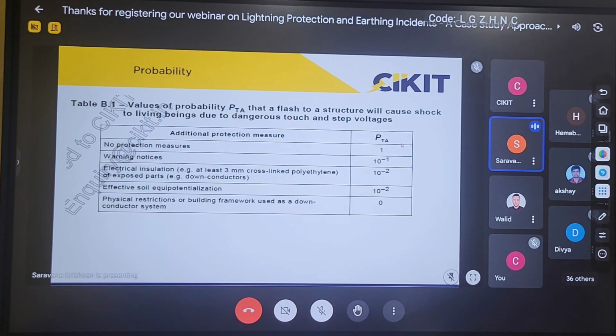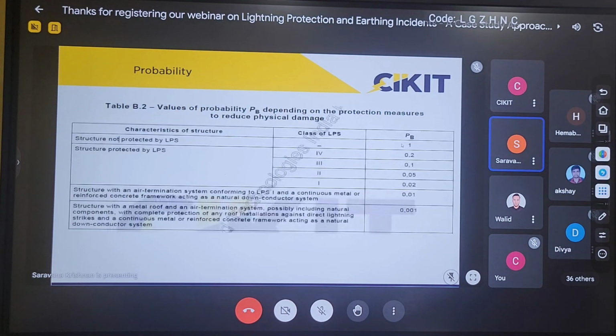So this is the next probability, PB. Here you can observe that if there is no lightning protection system, the value of PB will be considered as 1. If my structure is protected by a lightning protection system, then, depending upon the level of protection, the value of PB will be different. For example, while performing the risk assessment calculation, I will first perform the calculation without a lightning protection system, and then I will substitute the value of PB as 1.